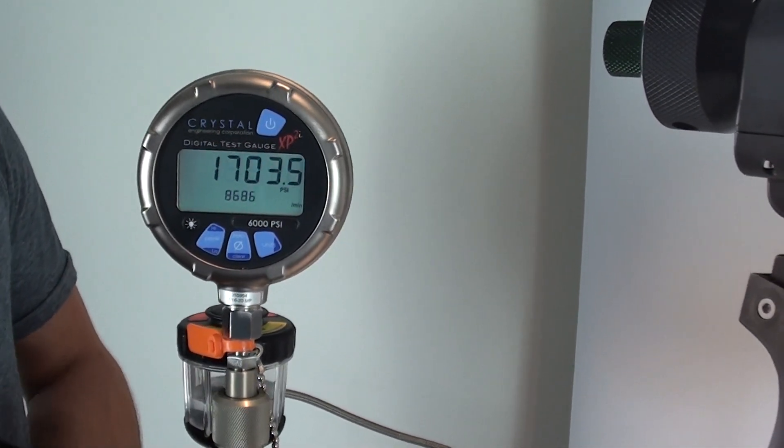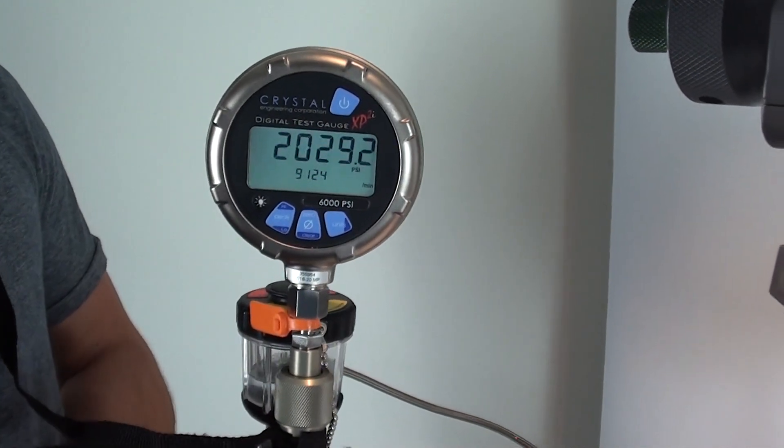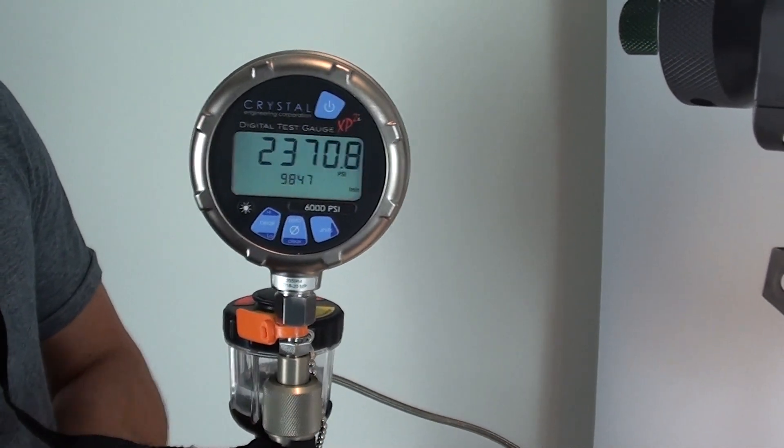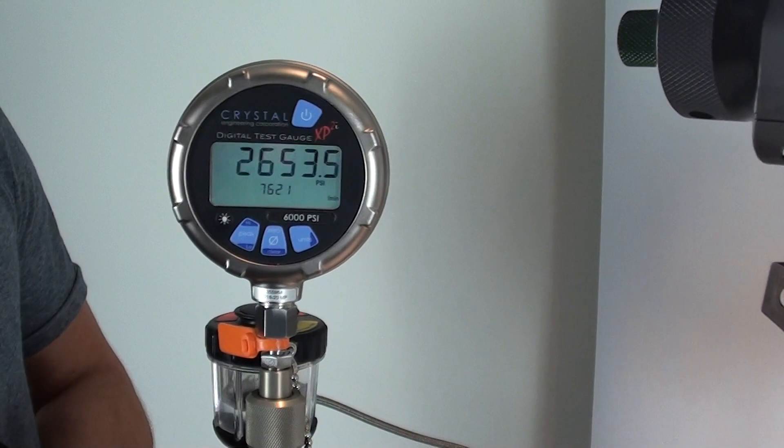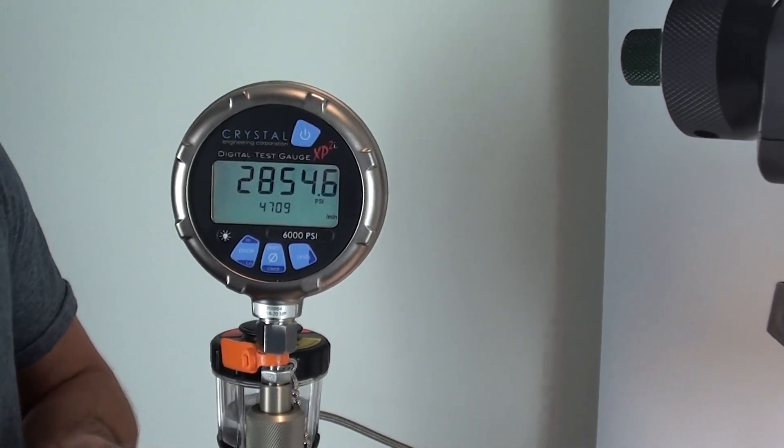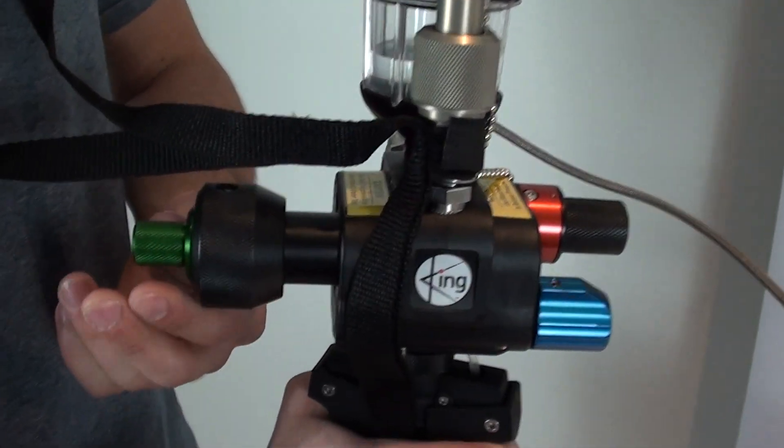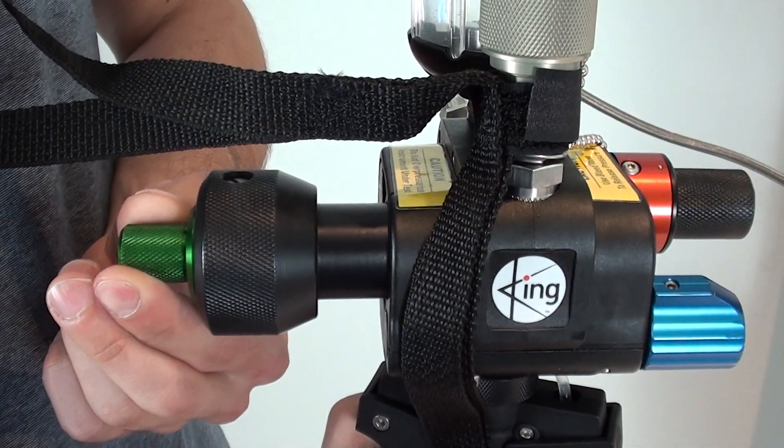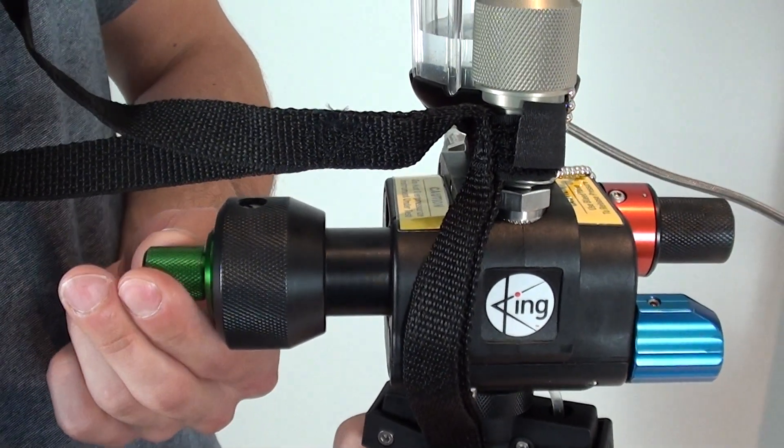So for the purposes of this test, we're going to go to about 3000 psi. As we get closer to 3000, what we're going to do is switch from using the coarse knob, which is the black knob, to the fine adjustment using the green knob.